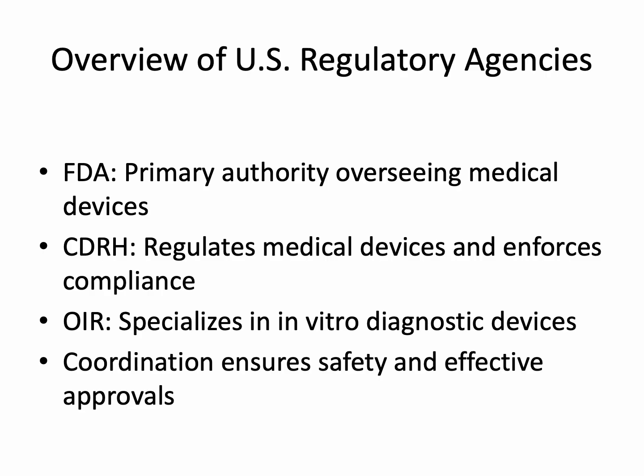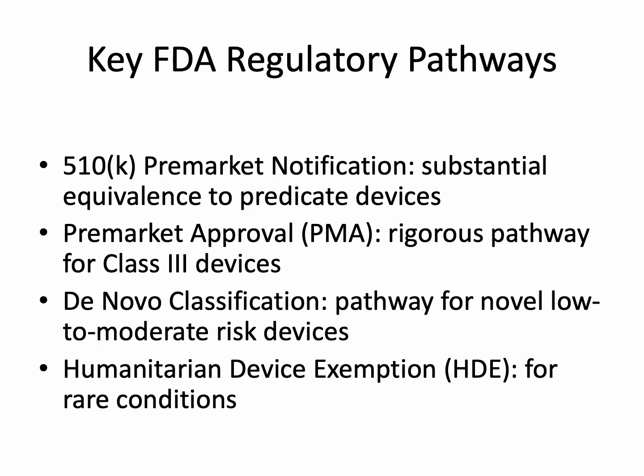Effective navigation of these regulatory bodies requires a deep understanding of their review processes, timelines, and expectations for documentation, testing, and clinical data. The FDA regulates devices through multiple pathways designed to balance timely access with patient safety. The 510(k) pathway is the most common, allowing devices that are substantially equivalent to an existing legally marketed device to reach the market with limited clinical data. The PMA pathway applies to high-risk Class 3 devices, requiring comprehensive clinical trials, non-clinical testing, and sometimes advisory panel review to ensure safety and effectiveness.